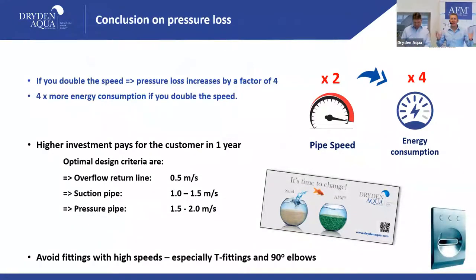Okay, so the takeaway is pipe speed is important. If you double your pipe speed, your energy consumption and pressure loss will quadruple. And I'm not going to mention it for the fifth time, but suction pipe is 1 to 1.5 meters, pressure pipe 1.5 to 2 meters.